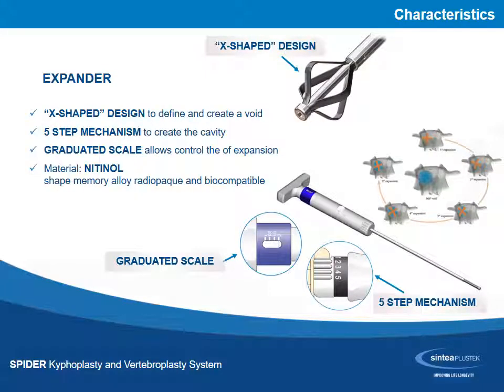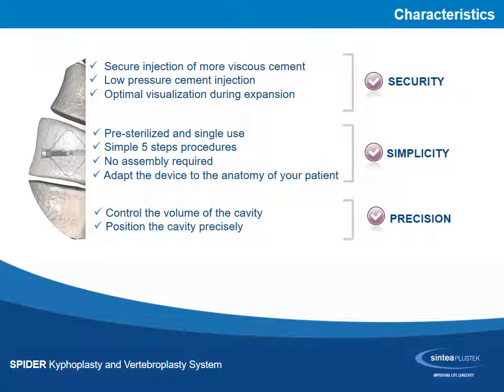The expander has an X-shaped design to define and create void, a 5-step mechanism to create the cavity, and a graduated scale that allows control of the expansion. The expander is made of nitinol, a radiopaque and biocompatible shape memory alloy. The system is secure for cement injection and optimal visualization during the expansion, simple, pre-sterilized and single-use, with a simple 5-step procedure. It adapts the device to the anatomy of the patient, and is precise, with control of the volume and position of the cavity.